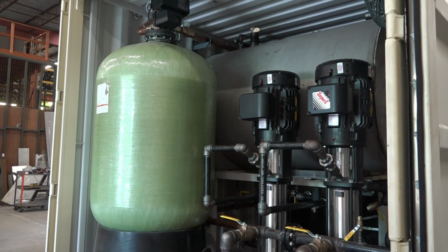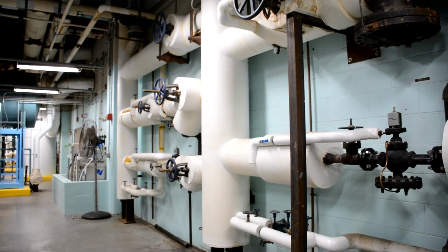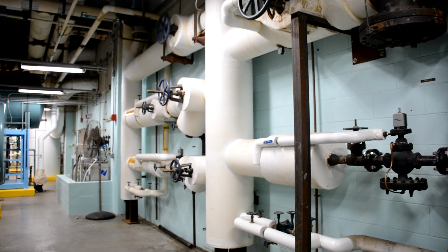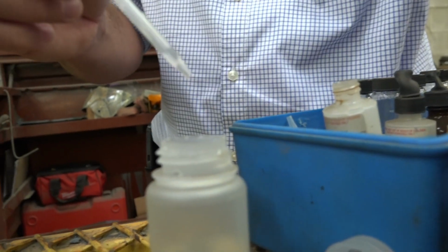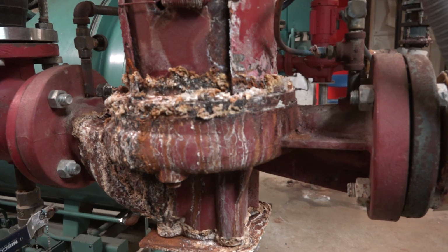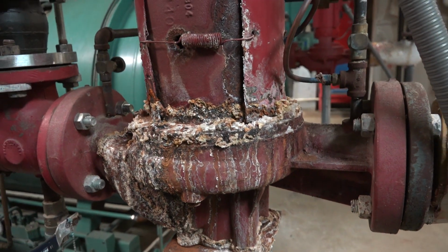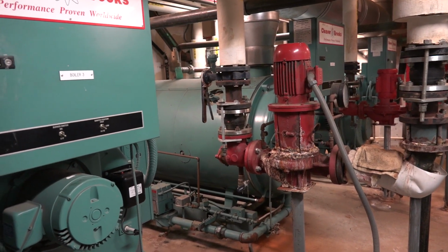Another note worth mentioning is the waterside care. As discussed in many of our videos, as temperature and pressure increase in a boiler, the water inside the systems becomes more suspect to causing damage to the system. In other words, a hot water boiler is generally less susceptible than a steam system is to the waterside damage, whereas a high pressure steam system will need a more strategic water treatment plan, including regular blowdowns. Hot water boilers can still be troublesome with dissolved gases present in the system. Generally, a chemical plan can control these alone, but more importantly, monitoring the system regularly for leaks is important. Leaks allow for air to enter the system and then create problems throughout the entire hot water loop. So regular maintenance and monitoring of all systems is critical.